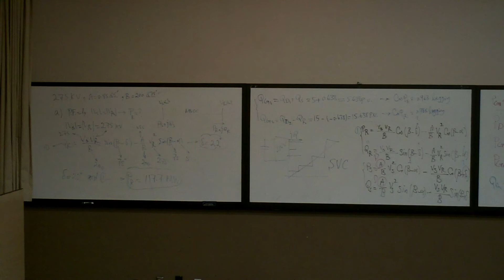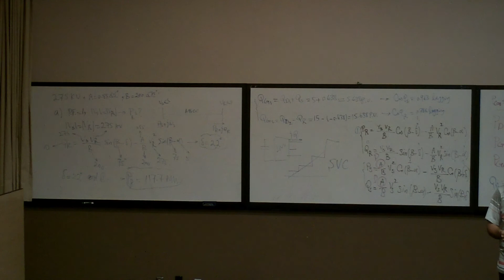Now the question is this: what type and rating of compensation equipment would be required? It says, first of all, tell me, to get this voltage, I want to have 275. Tell me what should I install here. A capacitor. So the answer, I'm not going to install a generator because it's expensive, right? I'll go with my cheaper choice, the capacitor here. But he's asking, tell me how much rating, how much the capacitor should generate. What's the Q rating of the capacitor? He's asking what type of equipment. We said capacitor, but how much? We need to calculate that. How much we're going to put there. What type and rating of compensation equipment would be required if the load is 150 megawatts?